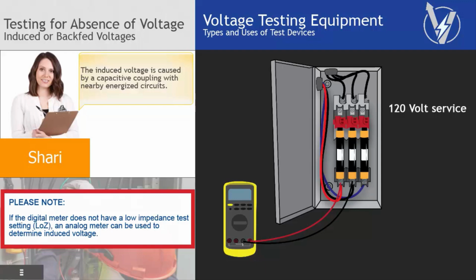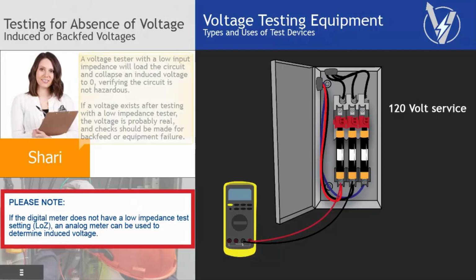The induced voltage is caused by a capacitive coupling with nearby energized circuits. A voltage tester with a low input impedance will load the circuit and collapse an induced voltage to 0, verifying the circuit is not hazardous. If a voltage exists after testing with a low impedance tester, the voltage is probably real, and checks should be made for backfeed or equipment failure.